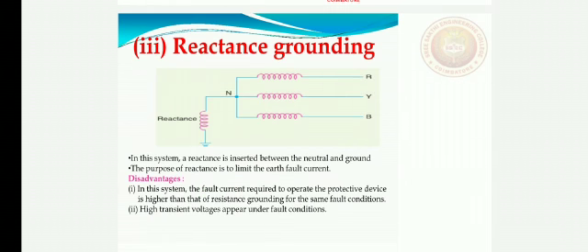Third one, reactance grounding. In this system, a reactance is inserted between neutral and the ground. The purpose of the reactance is to limit the earth fault current. In this system, instead of resistance, a reactance is connected between neutral and earth with a ratio of reactance to resistance more than 3. In addition to the zero sequence impedance of the source and faulty phase up to the point of fault, the fault current is dependent on the reactance.